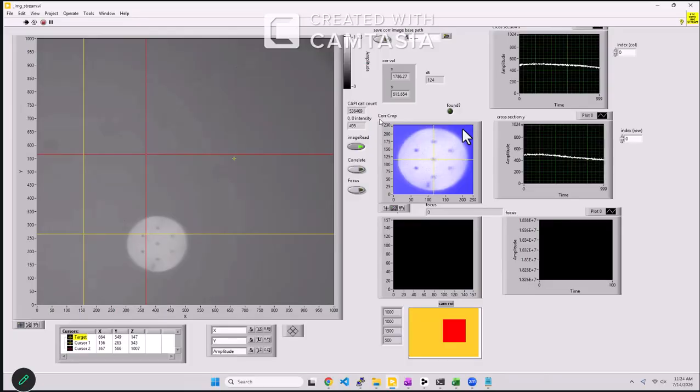And because the camera is fixed relative to the system, in the future, any time that you attach a different sensor, which may slightly vary in X and Y and Z compared to the golden sensor that you use during calibration, since you have that reference image position, as long as you drive it to the same reference position, you'll get coupling. That is because of the fact that the image sensor is fixed relative to the rest of the system, regardless of what instrument that you put on it.